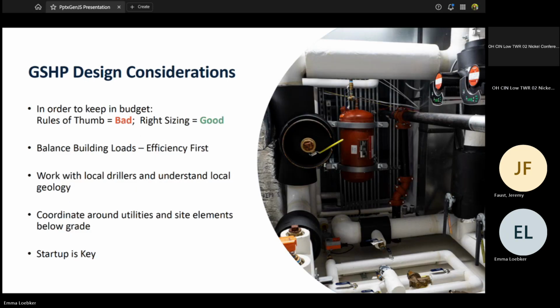At a building scale, for an individual project, if you want to keep project costs manageable—since closed loop systems can get very large and expensive—you don't want to rely on rules of thumb for design. You want detailed, right-sized systems, studying the local geology carefully. Having the data set that's part of this report is important so we understand ground conductivity, achievable flow rates, and how to right-size systems so we're not throwing money away on oversized installations.